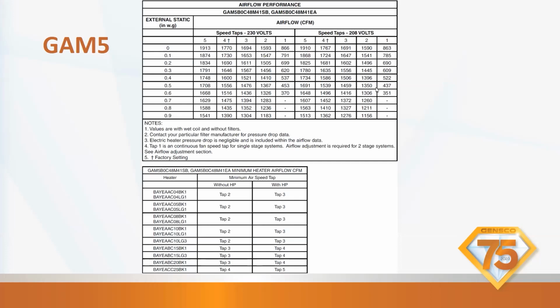Now, when we're doing an air handler, you also need to look at the chart that's on the bottom there. That is the minimum speed with different heaters. Okay. So with that BAYEABC15BK1, your minimum speed with a heat pump is tap 4. So you cannot put it on tap 3 or tap 2. You have to use tap 4.